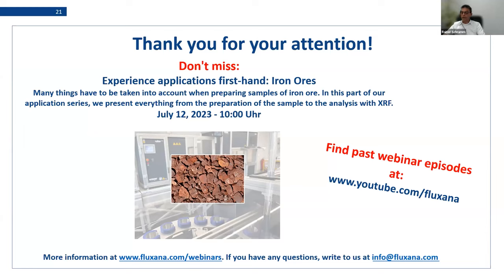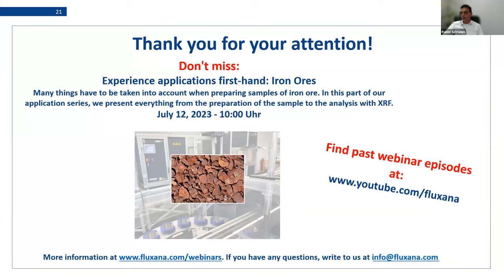Next question: if I have a sample with a low Compton ratio, how can I increase it to 100 percent? Compton ratio means Compton-to-Rayleigh ratio. If this is low it means you have very little scattering, and then this correction approach comes to a limit. You have to check whether the Compton scattering is really independent of your element concentrations and try it out by testing. For the Compton scattering correction, it works very well when the analyte line is very close to the Compton line. The farther away, the less it works. If there is an absorption edge in between, that will also disturb the ratio and the correction may not work.